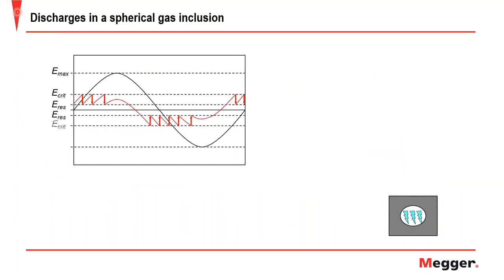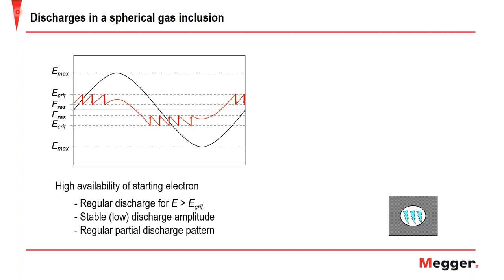And here we have discharges in a spherical gas inclusion. In this particular case, we're talking about having the high availability of a starting electron. So with the high availability of a starting electron, there would always be an electron available once the critical field is met. So the partial discharge occurs when the critical field is reached. Then the internal field breaks down to the residual field, and then it would charge again, and then discharge again once the critical field is reached. And this causes a consecutive row of even pulses, and then the changing of the opposite polarity, and then again, once the critical field is met, discharge occurs, and this causes a phase shift, in this case, in the first and third quarters.